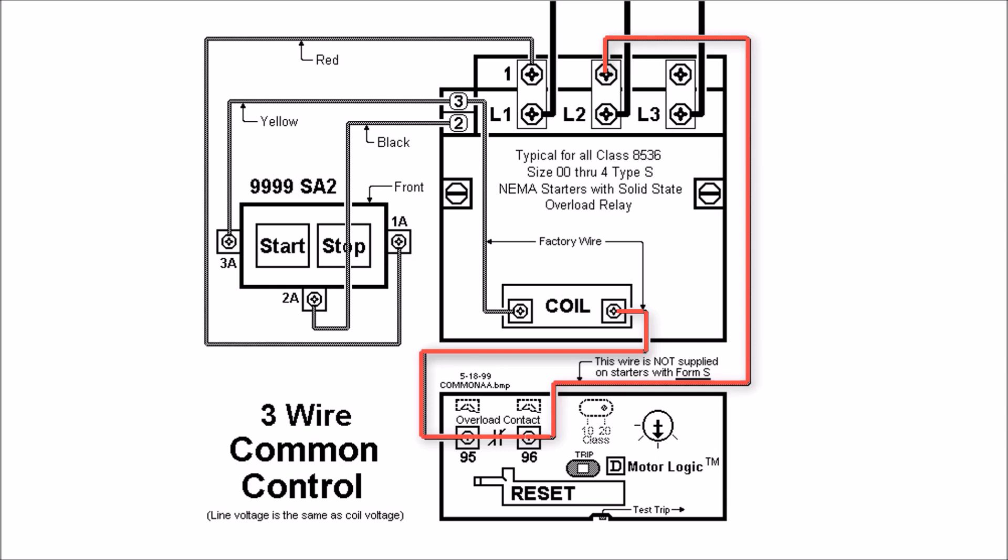The left hand side your coil will again be connected to terminal 3 of your holding circuit contact and the only other change for this is going to be a control takeoff wire that you will install from terminal 1 on your control takeoff over to 1A. Everything else has the same connection points.